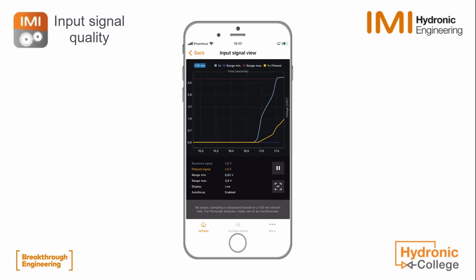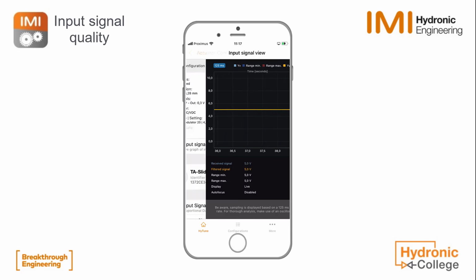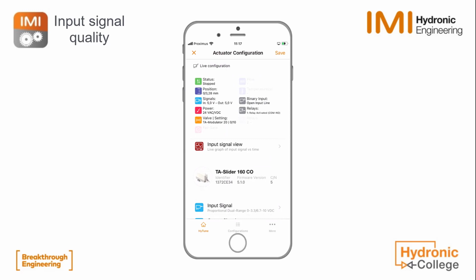When I go up to 5 volts now, you see that the filtered signal is following the blue line, but we reach a stable line, a stable blue line, so the input signal is stable and the filtered value is of course also stable. So this function is always useful when you remark that an actuator is constantly moving or seems not to be able to close the valve fully.